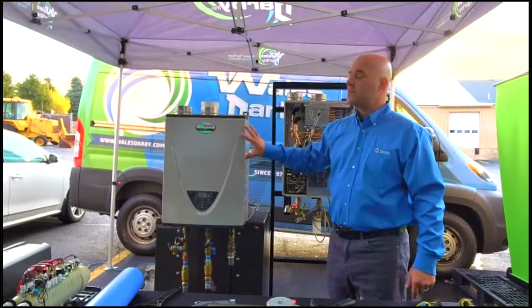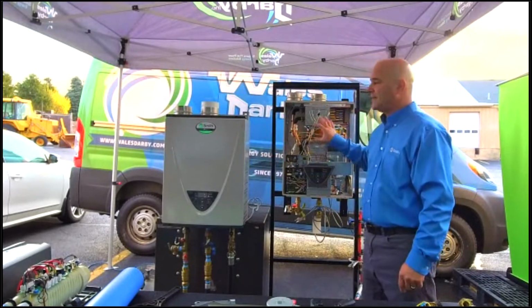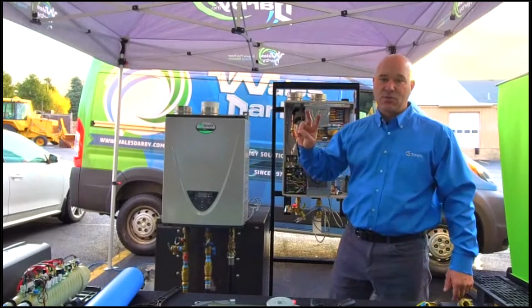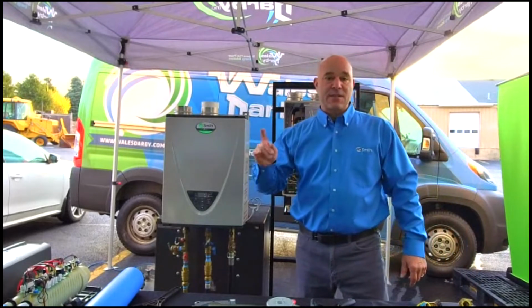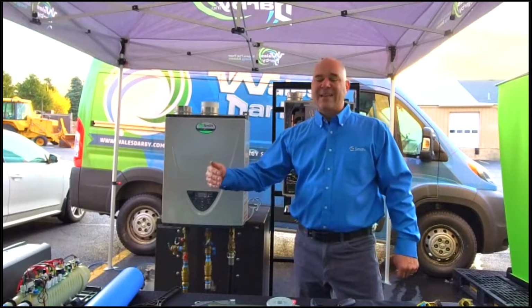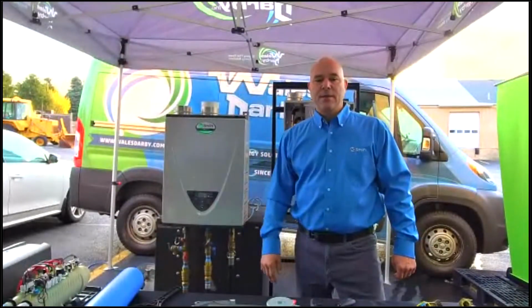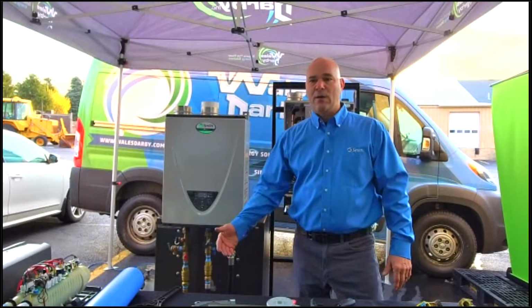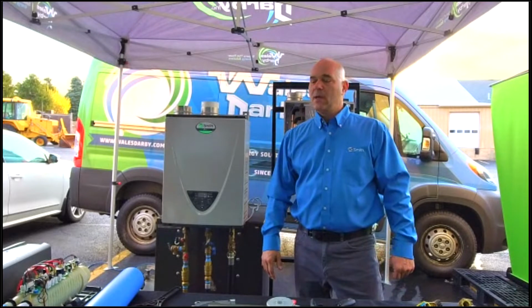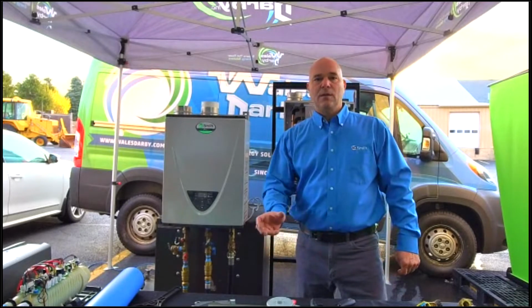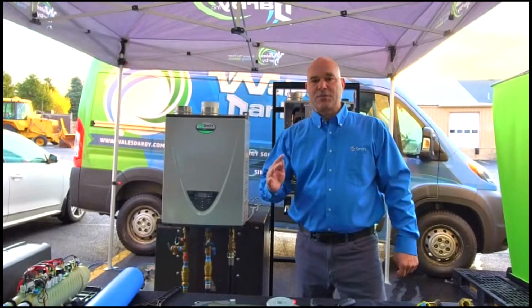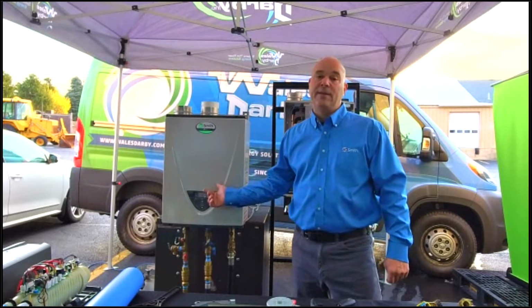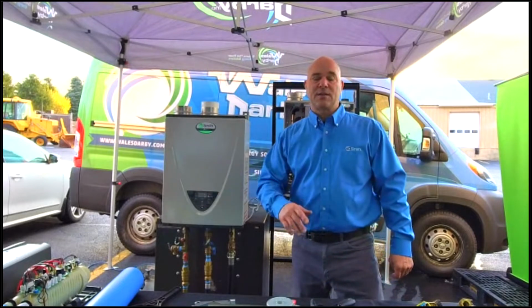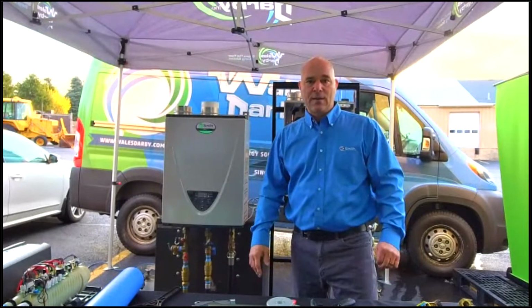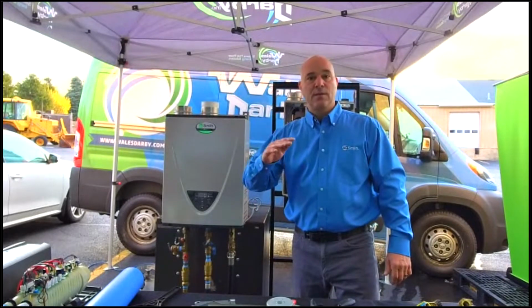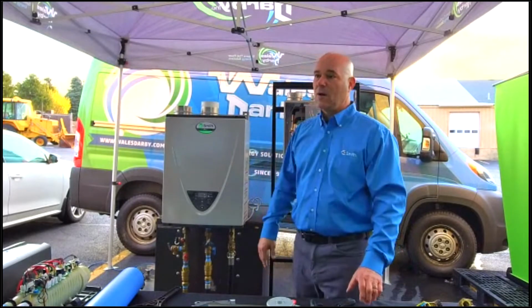Pressure drop across the heat exchangers. These are what you're looking at here. These are both condensing heaters. So condensing heaters have 2 heat exchangers. Non-condensing heaters have 1 heat exchanger. If you're going to put a tankless style heater into a situation where the homeowner has a well to support their home for domestic water, you would probably want to stick to the non-condensing version. Based on the pressure switch and the pressure drop across a tankless water heater, you're going to want to probably stick to a non-condensing because the pressure drop is much lower, and that will work better with the 20, 40, 30, 50 well tank that they have within the home.